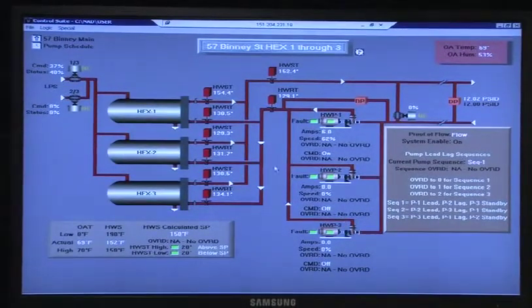Anyway, let's go through it real quick so we understand. So we've got proof of flow, which is this. Proof of flow is right there, see where it says pressure pumps, DP? That's the flow switch, that's your differential pressure on your right-hand side there. Okay. So it's a manual system enable, it's not based on outside air, I believe. It's hot water year round, so you never reheat. Yes, it's pretty much on all the time.